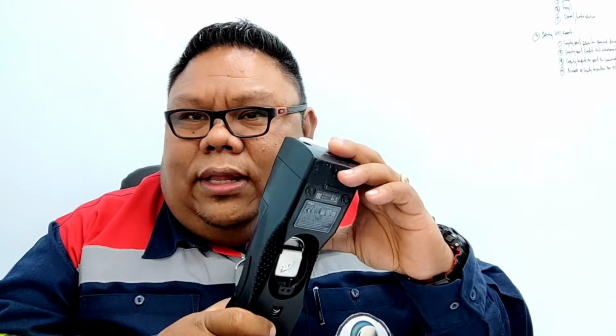By sending this unit to the external calibration center, we ensure the accuracy of the reading it provides to the gas detector specialist or gas test qualified person — that this unit has passed the quality test or external testing and calibration. This one they have, but actually this is the vendor HEBA.